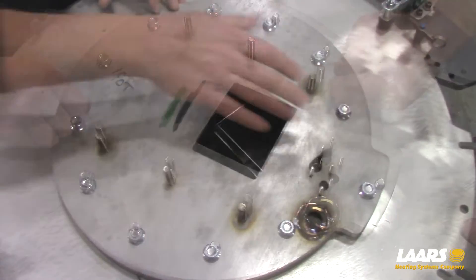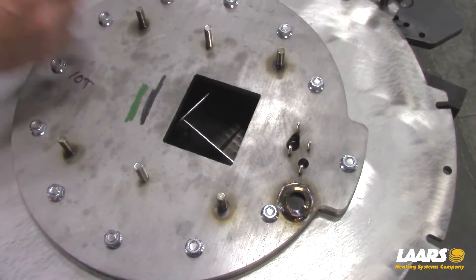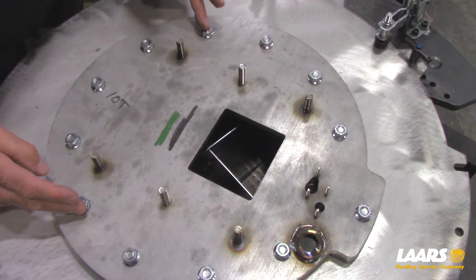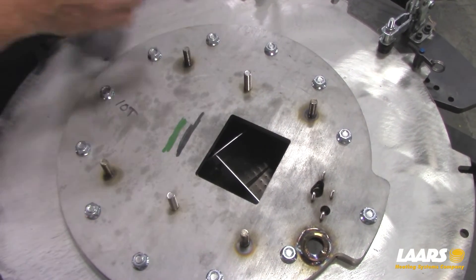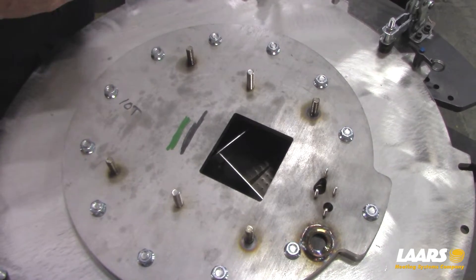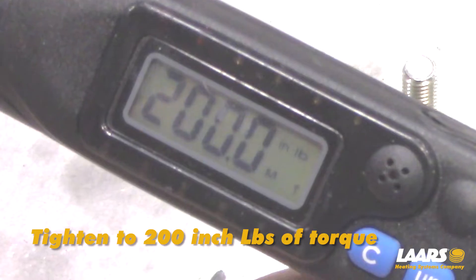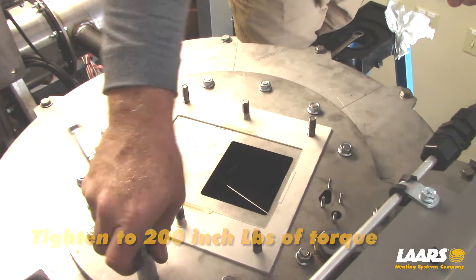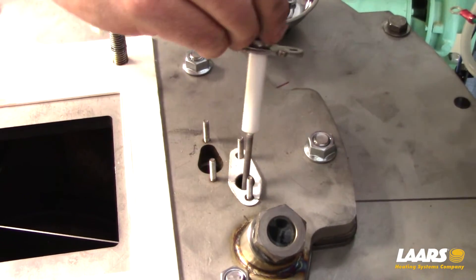Start tightening at the bolt where the smaller gaskets are. Tighten in a triangle pattern — start with this one, and then these two here. Tighten at multiple different points, always in a triangle pattern relative to each other. The torque wrench is set to 200 inch-pounds of torque. Continue with the rest of the reassembly.